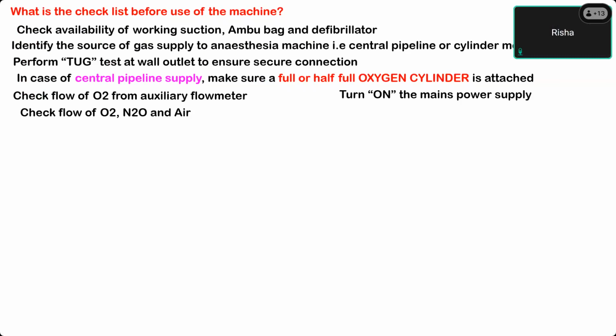To raise the nitrous oxide above the oxygen level, like 3:1, close the oxygen flow meter, then nitrous will also be... No, if the oxygen flow meter knob is in the closed position, by opening nitrous oxide, will you be able to get oxygen flow also? No, sir. Will the nitrous oxide first of all flow if you open the nitrous oxide knob without opening the oxygen? No, sir.